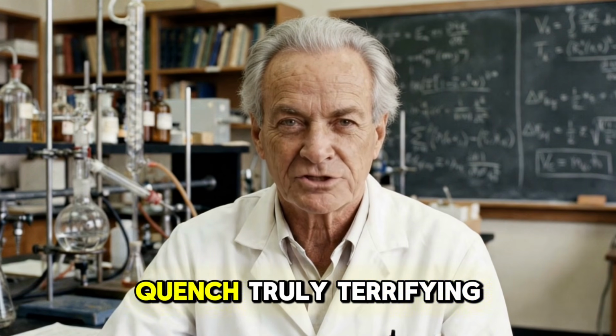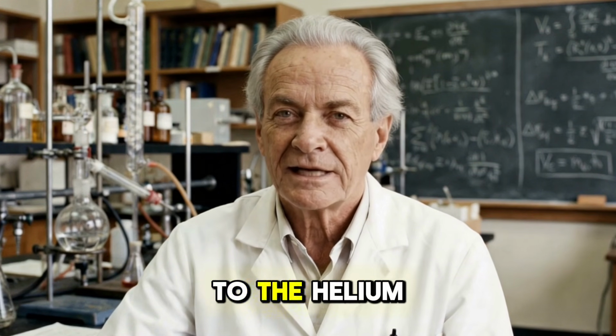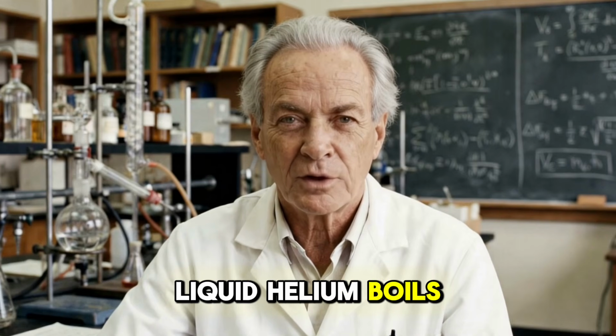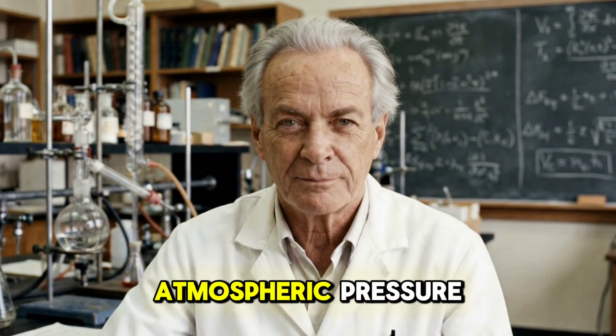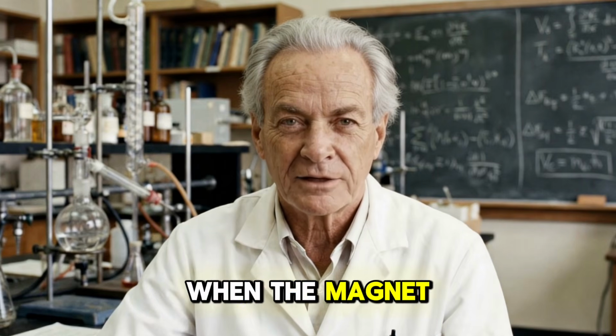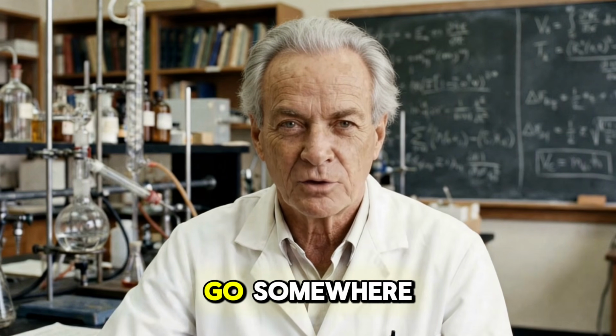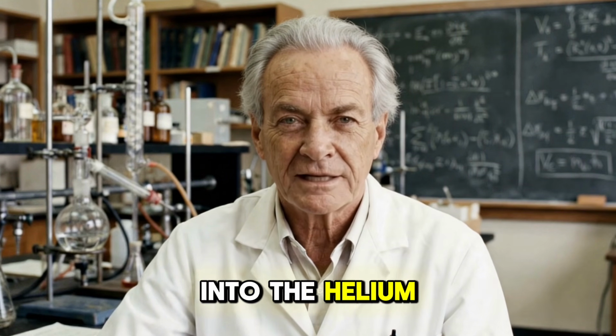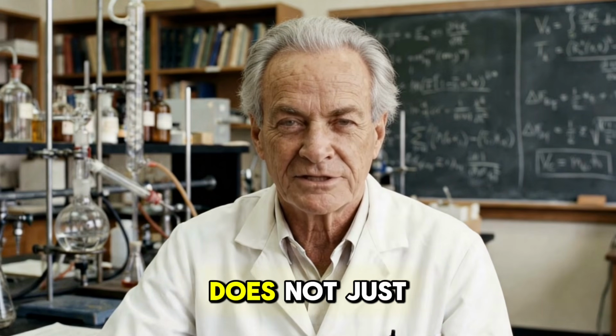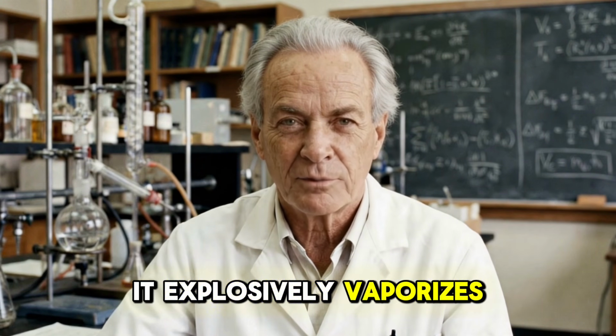What makes a quench truly terrifying is what happens to the helium. Liquid helium boils at 4.2 Kelvin. That is its boiling point at atmospheric pressure. When the magnet quenches, all that dumped energy has to go somewhere, and it goes into the helium bath. The liquid helium does not just warm up, it explosively vaporizes.